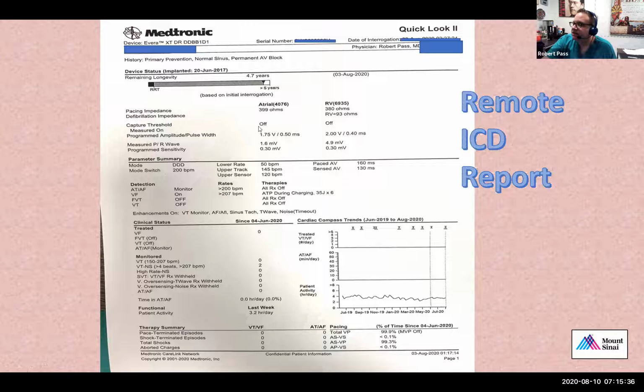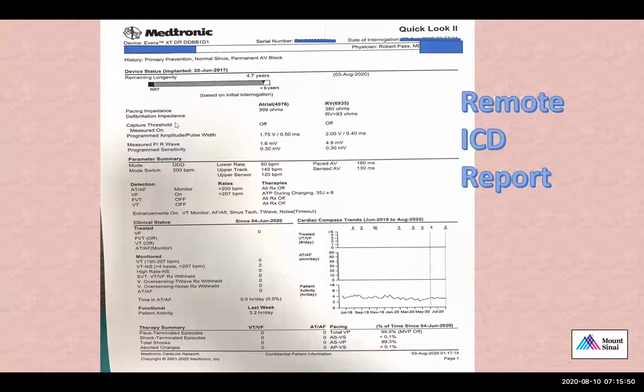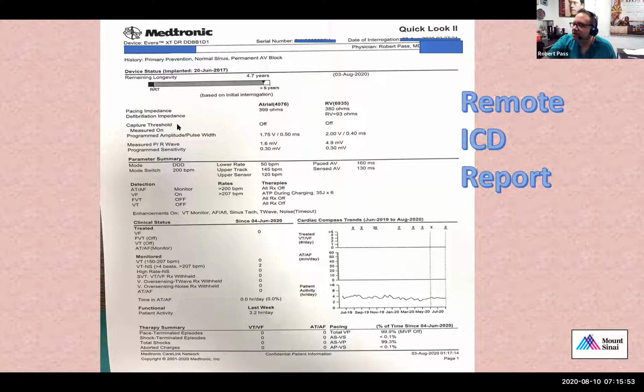In this particular case, I have capture threshold off. Does anybody know what capture threshold is? Let me ask Perna. Are you familiar with that term, or do you know what that means? No, Dr. Pat. Okay, so capture threshold is a system where the pacemaker can actually measure the threshold from beat to beat and adjust the output accordingly. The theoretical benefit of this is that, normally when we program a pacemaker permanently, we set the outputs at roughly double the threshold. And as you know, the threshold is how much energy is required to pace the heart.